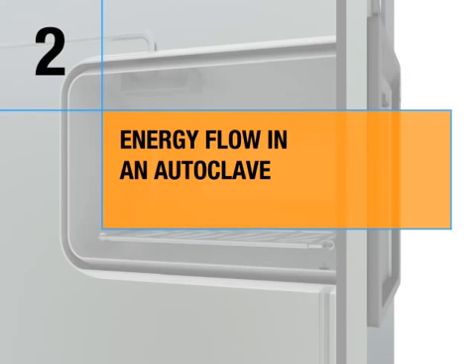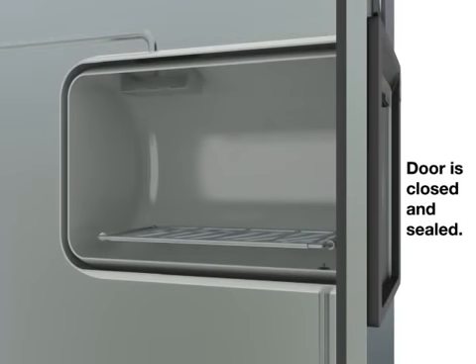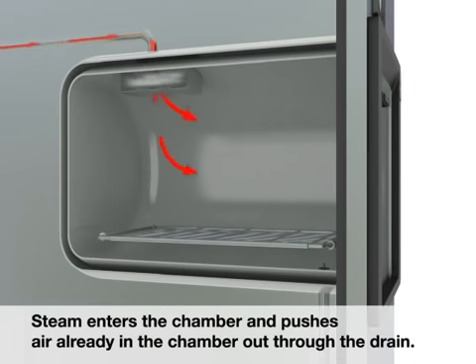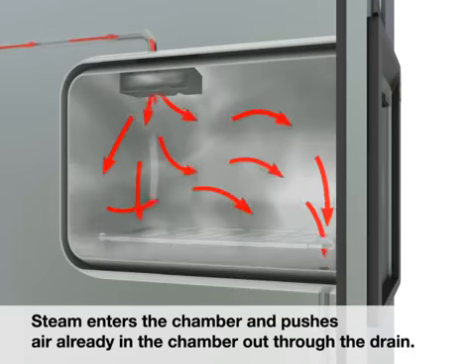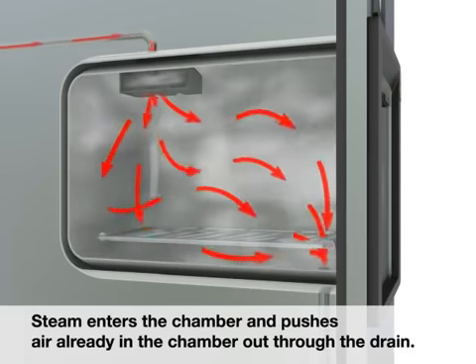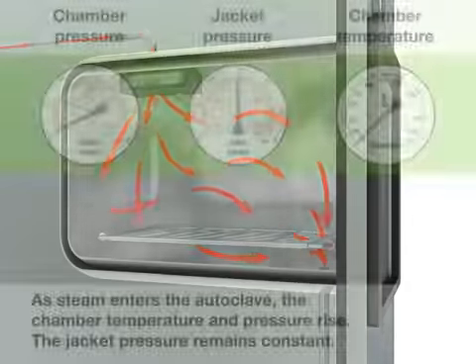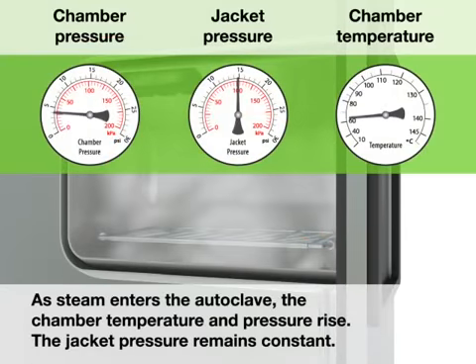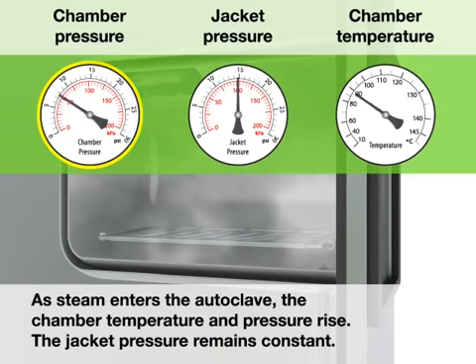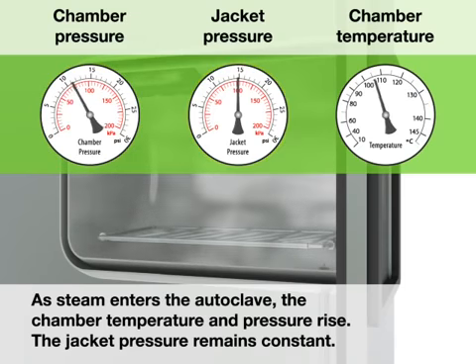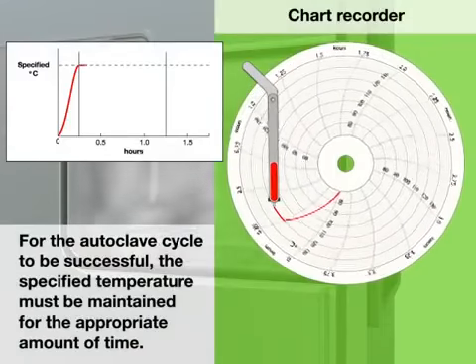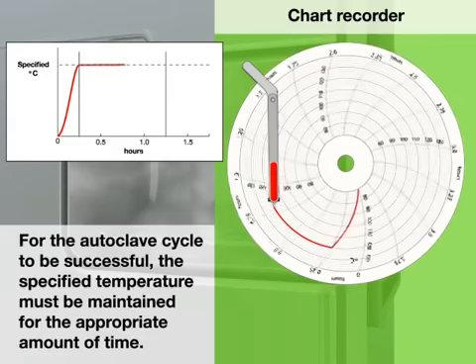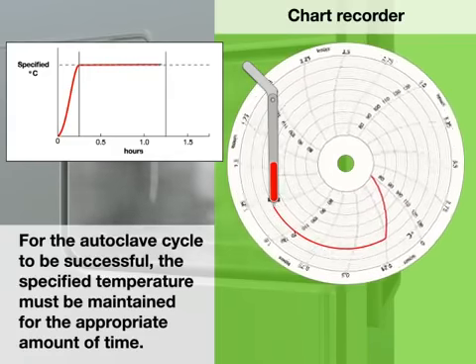Energy flow in an autoclave. Door is closed and sealed. Steam enters the chamber and pushes air already in the chamber out through the drain. As steam enters the autoclave, the chamber temperature and pressure rise. The jacket pressure remains constant. For the autoclave cycle to be successful, the specified temperature must be maintained for the appropriate amount of time.